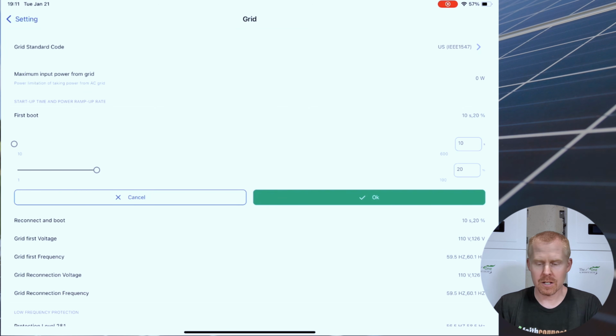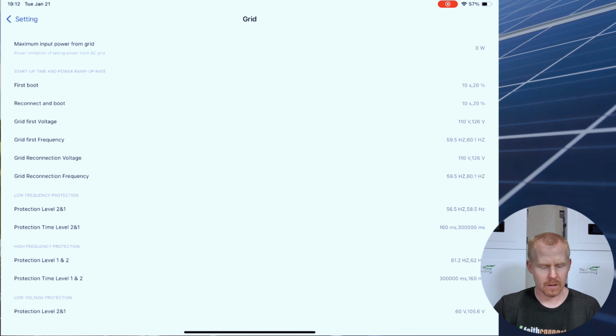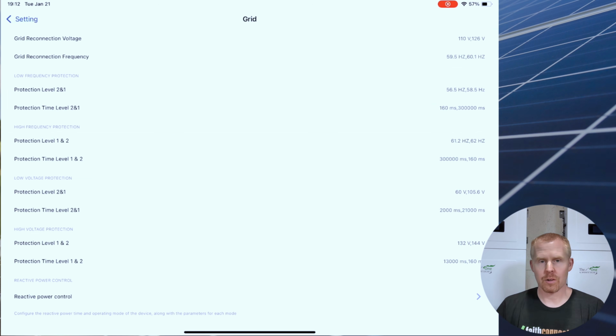So you can come in here, if you're not selling back to the grid, and change this value to 10 seconds startup time. And then the percentage is going to be the ramp up rate when it first turns on. By default, it's 20% per second ramp up. And it's the same with the reconnect and boot. I'm not sure if the reconnect is supposed to be for if you have an overload or something, when does it switch back?